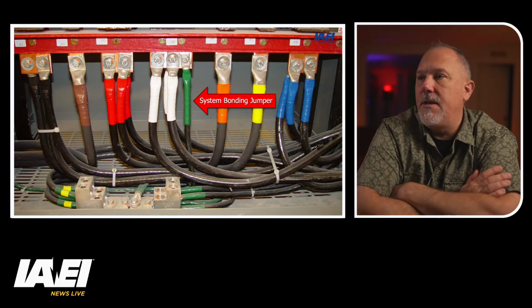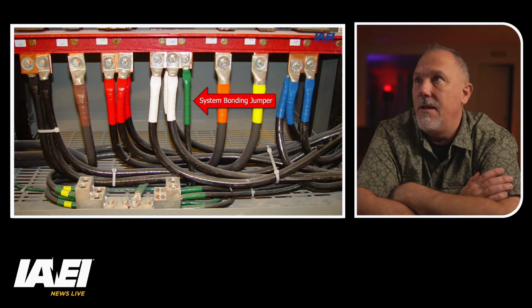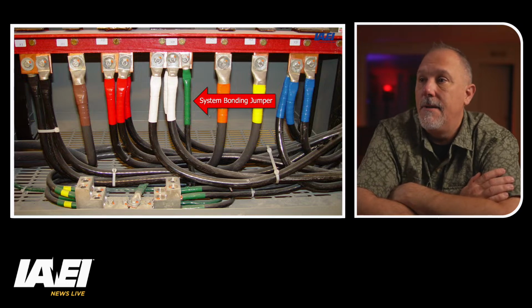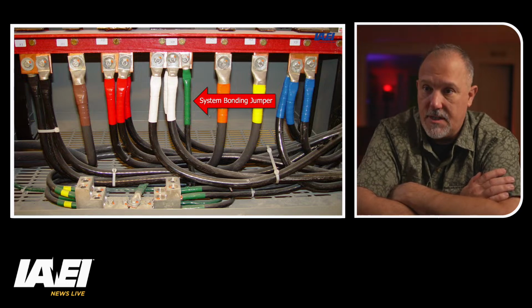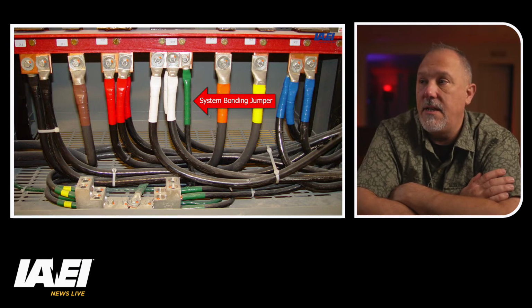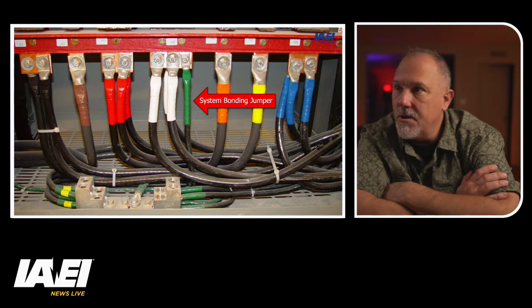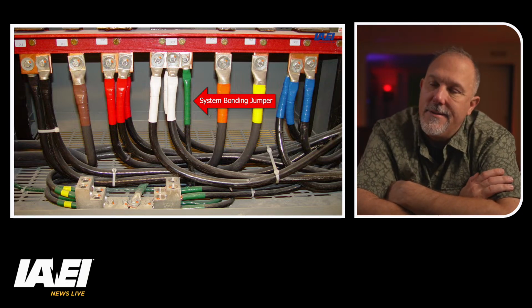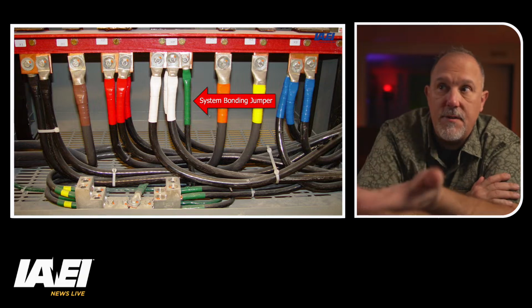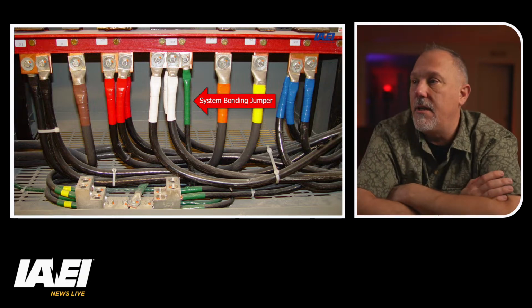There's your system bonding jumper in this application. There's your XO terminal, and you'll notice the lug down at the bottom of that transformer. And thank goodness they didn't put that over the vents, although all those conductors are right over those vents. I mean, it is what it is. Those vents are there for air to circulate up through.